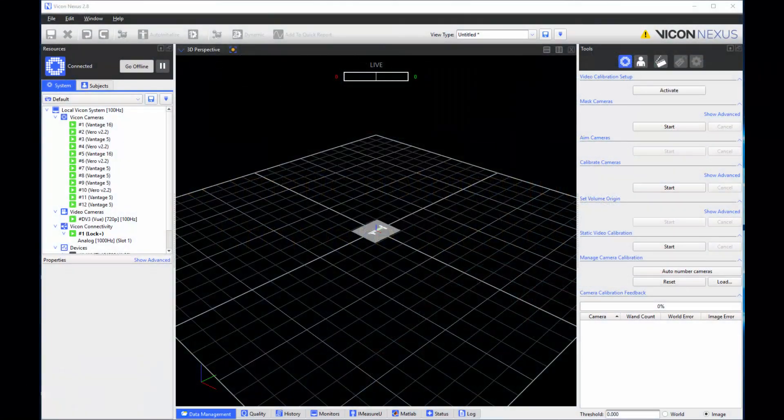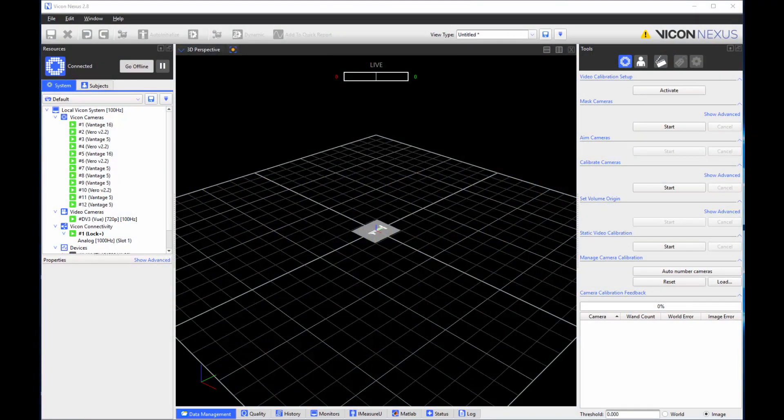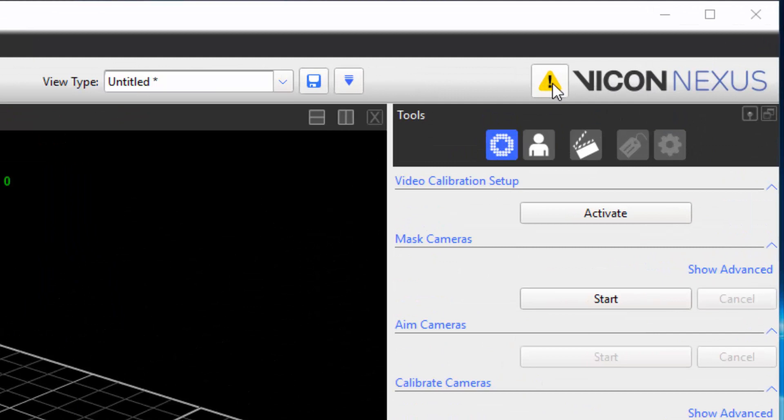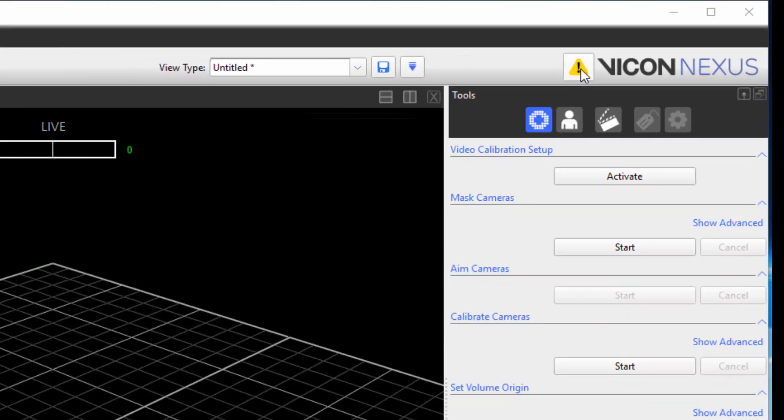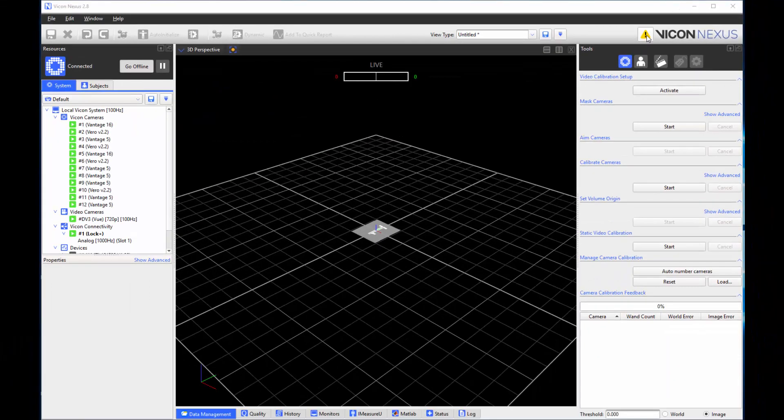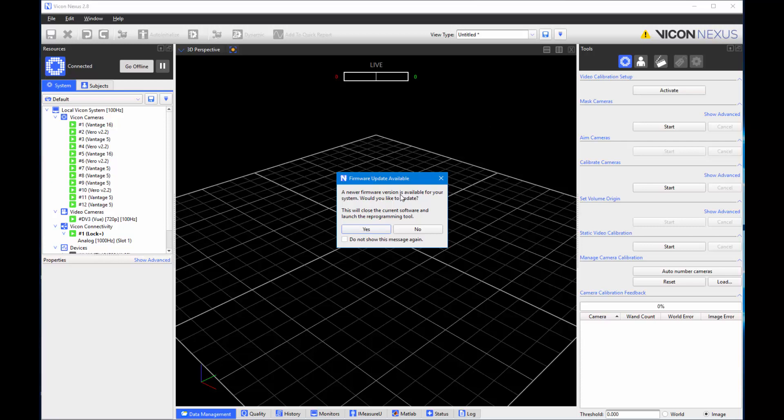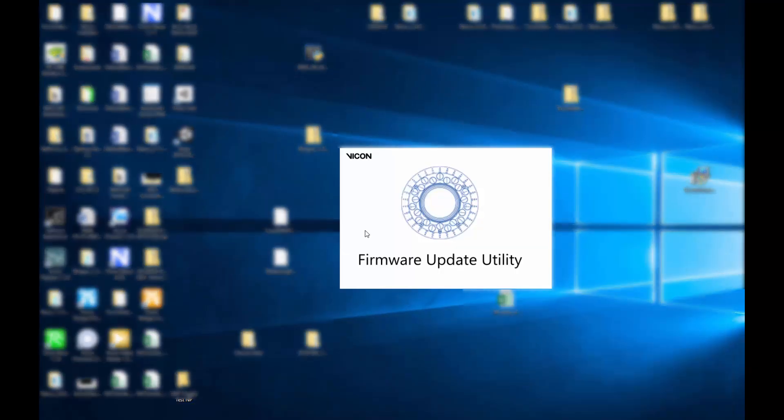Nexus 2.8 will now automatically notify you if any of your components are running on out-of-date firmware. If you have any devices that are not up-to-date, an icon will appear in the toolbar indicating that a newer firmware version is available. If you click on the icon, a new window will give you the option to close Nexus and launch the firmware reprogramming tool.